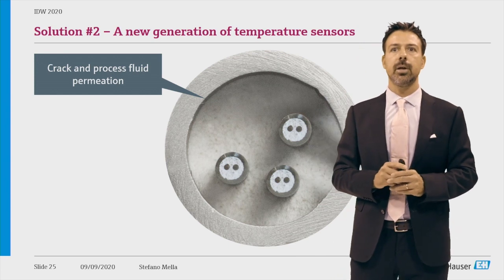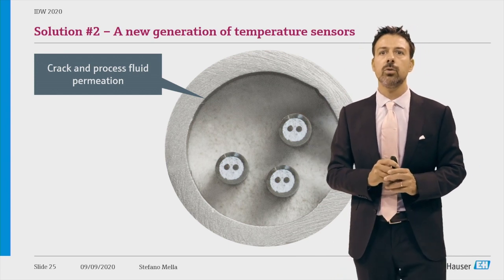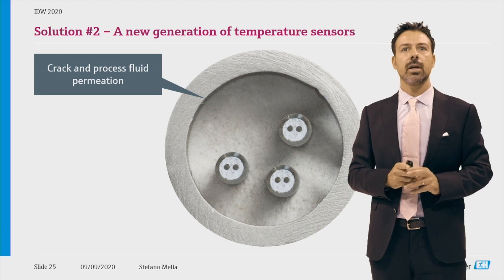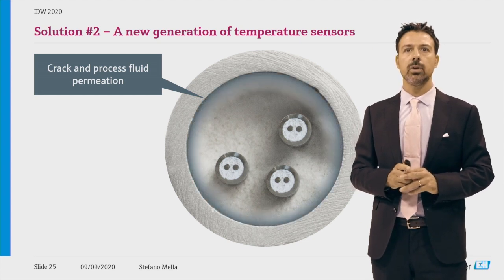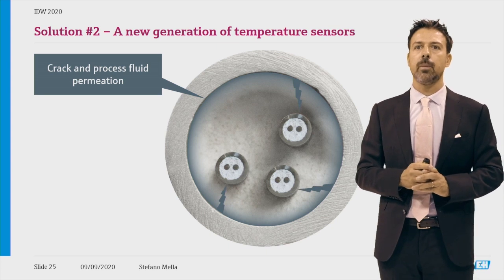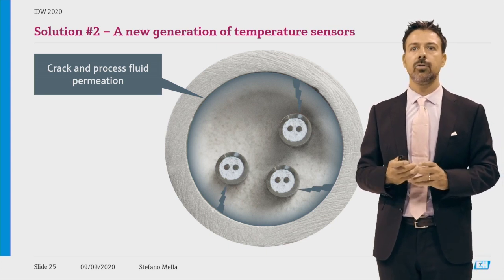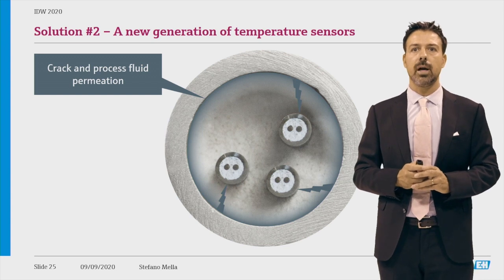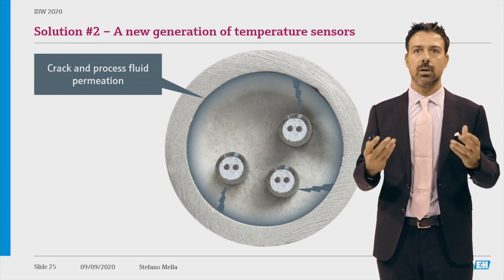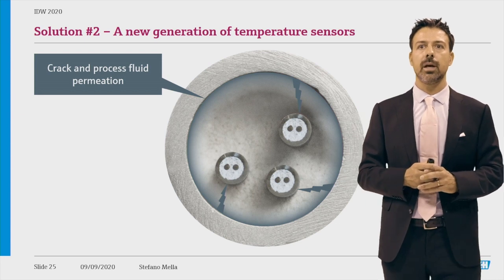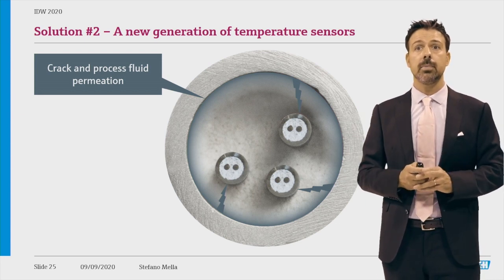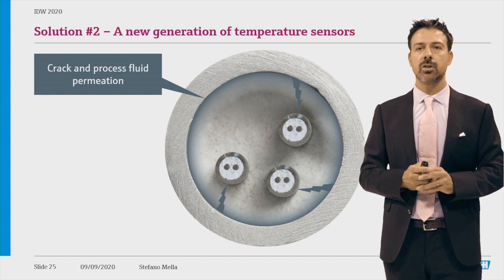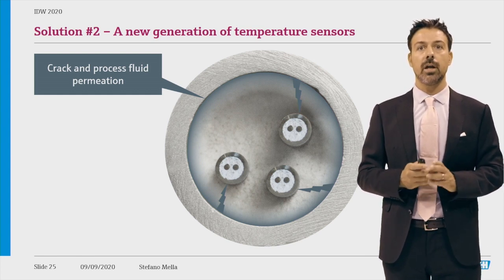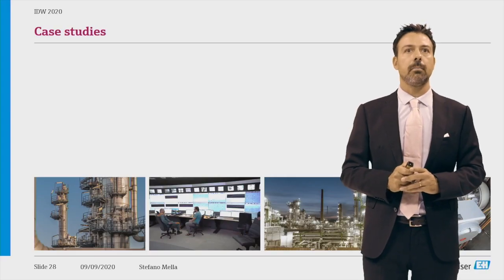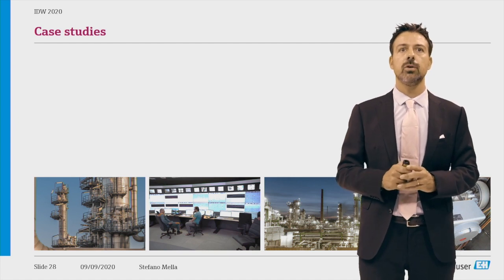I want to run again the animation we ran before with the new sensor. So in this case, again, we might have a crack, so the fluid can permeate through the profile sensor and diffuse on the mineral insulated powder, and from the inner sensors outside. So the contaminated area will be quite wide, but because of the inner dedicated sheath, the sensors are not affected at all from this contamination.